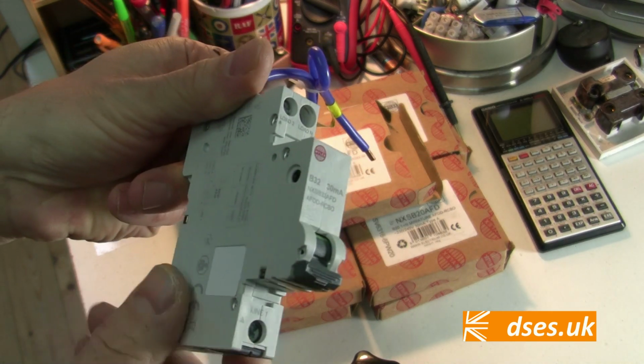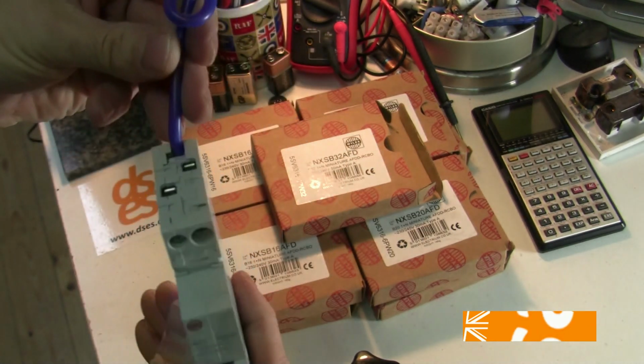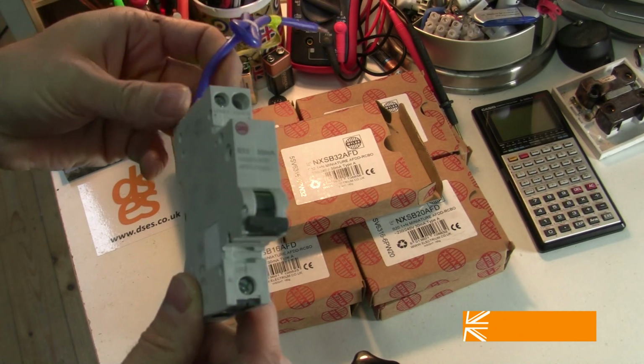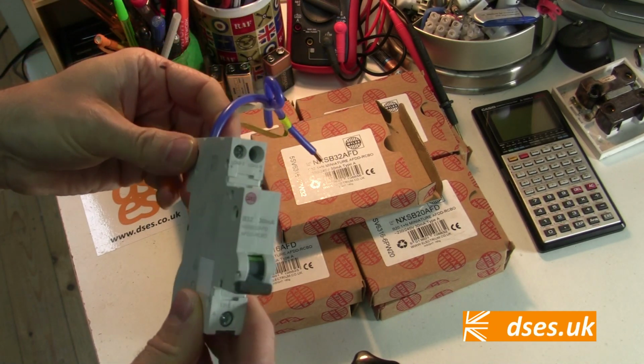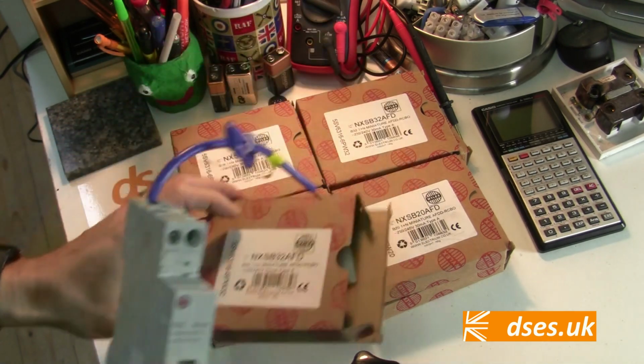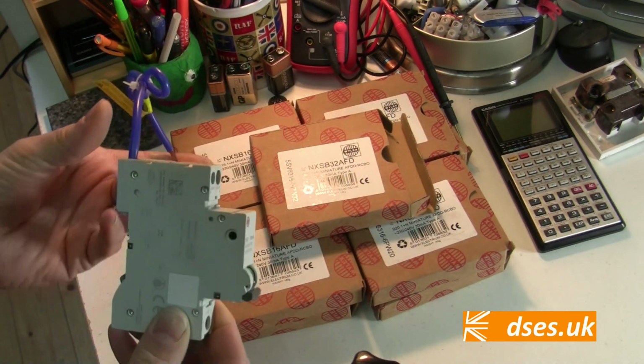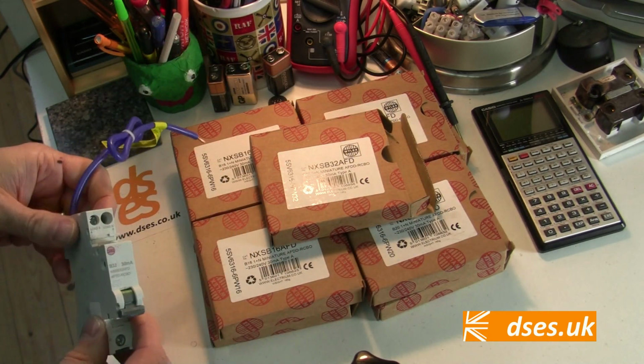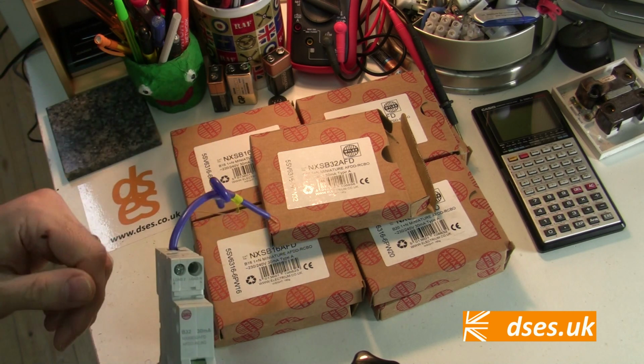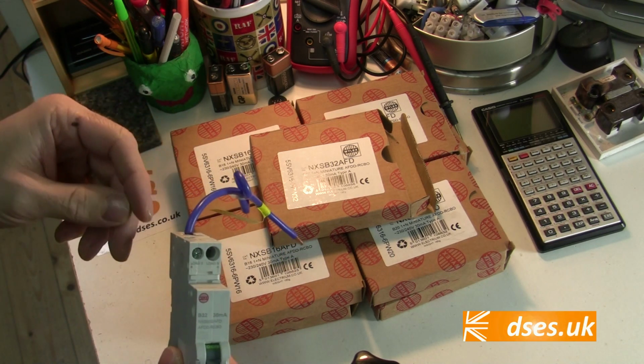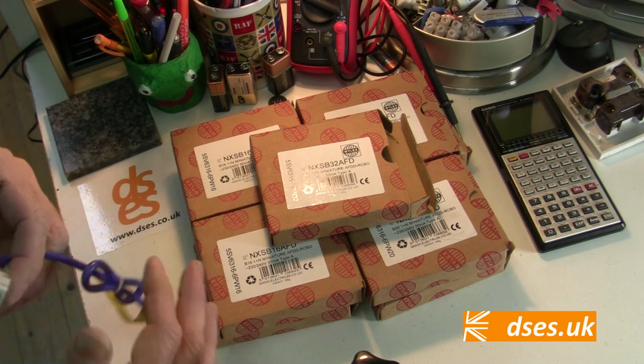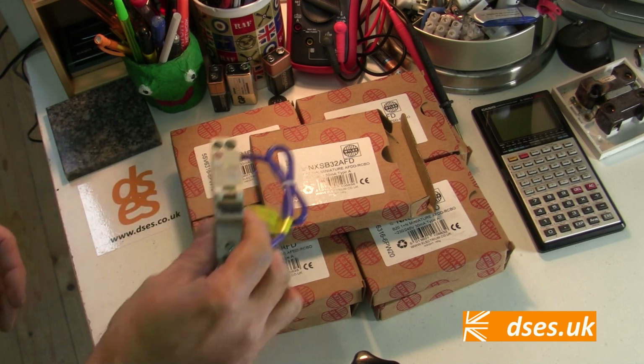AFCIs are nothing new over the pond, but are of course often employed on circuits that have a lower voltage and a higher current than is the norm in the UK. As far as I can tell though, they seem to be doing the same sort of job, which is to monitor the frequency of the current, the US unit's looking for a frequency of around 1 MHz according to Eaton, which would indicate arcing down the line and cause it to trip.